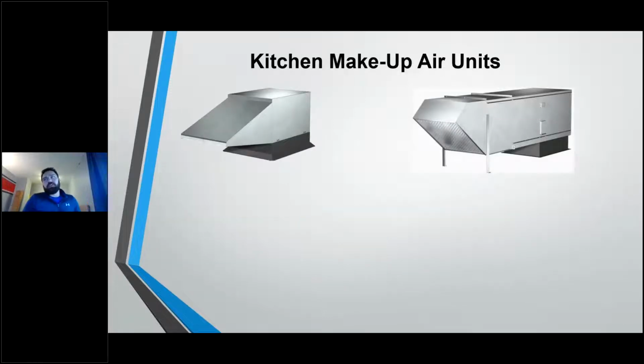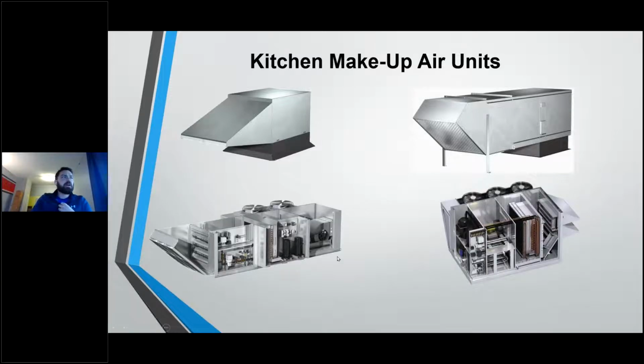Next component to a kitchen ventilation system is our makeup air unit. So I'm going to touch on a couple of different types of makeup air unit, again, regardless of manufacturer. And when we get into the portion where we're discussing a little bit of design, we'll talk about what we're seeing across the country when it comes to DX cooling or split DX cooling, DOAS units, dedicated outdoor air systems, or what is very common in the kitchen market, just a direct fired makeup air fan with no cooling on it. And we'll talk about why that is.